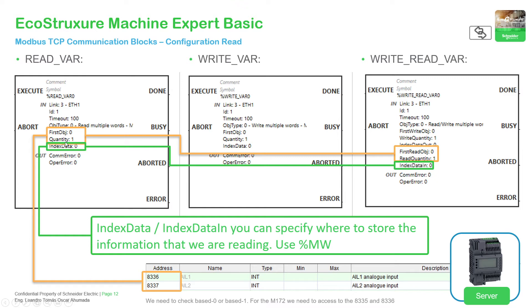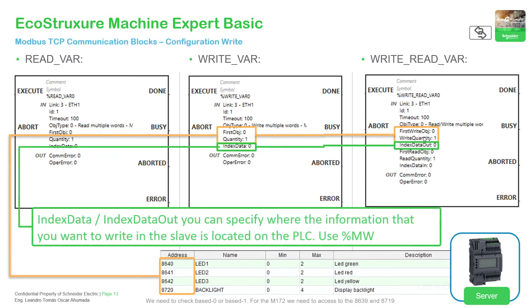You need to specify the first object on the other device, the quantity of memory words you want to read, and where that data is going to be located in the M221. So the first two parameters come from the other PLC or device, and the index data indicates where you want to locate the information in the M221. For the write direction, specify where to write the information on the other side, the amount of data, and where the M221 will take the data from to send to the other side.